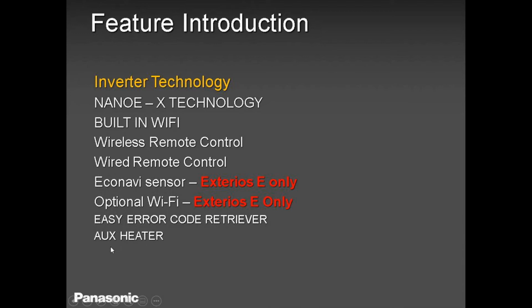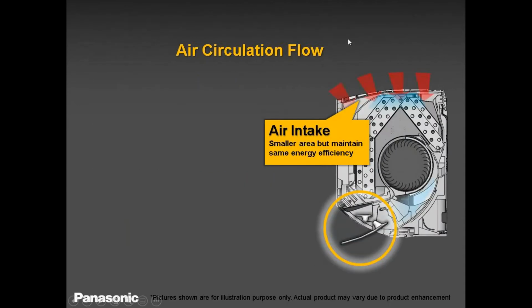And then our units are equipped with a plug-in auxiliary heater. Over here in Canada, some parts out in the East Coast, they use our heat pump as their primary source of heat. So sometimes when the temperature goes below minus 15 degrees Fahrenheit, the heat pump cannot keep up. It gives out a little bit of capacity. That way you can add on a baseboard heater or a hot water coil or anything. And that's the beauty about our indoor unit. There is a plug-in there. You get 12 volts DC. You can energize a relay and take it from there.